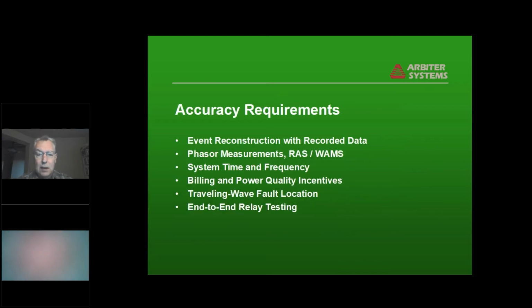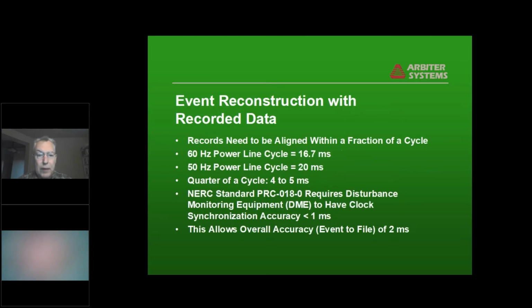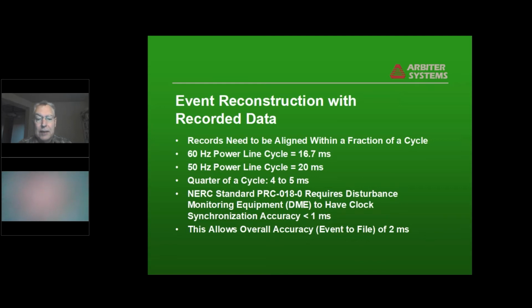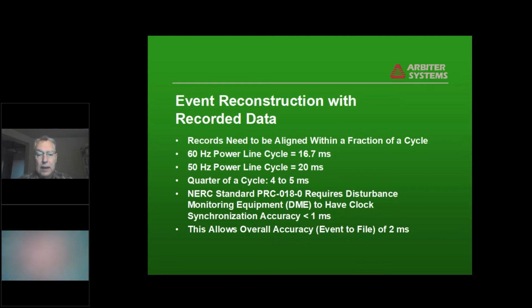So we're going to talk a little bit about the accuracy requirements for these different types of application. And you see the list of them there. We'll go right through it. For event reconstruction with recorded data, the data is most useful if it's recorded in a small fraction of a cycle, with accuracy of a fraction of a cycle. And there's the lengths of power line cycles of 50 and 60 hertz. A quarter of a cycle is 4 or 5 milliseconds.